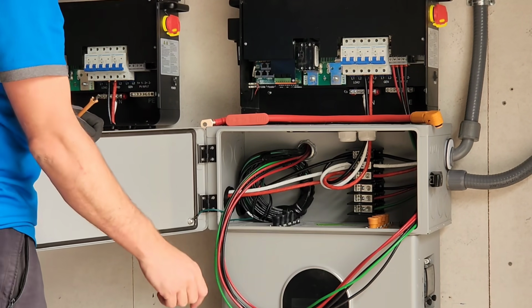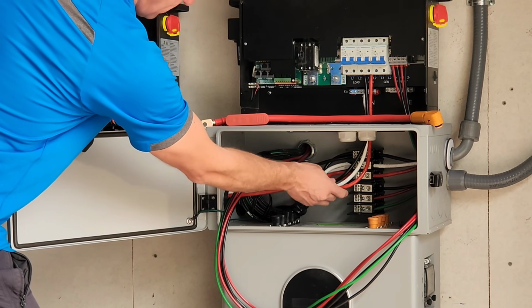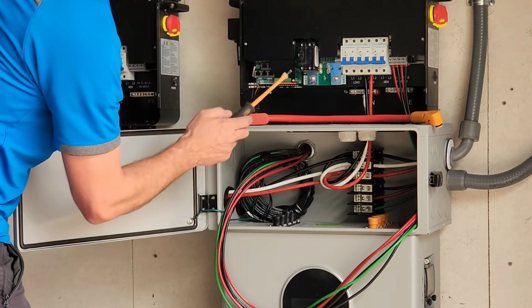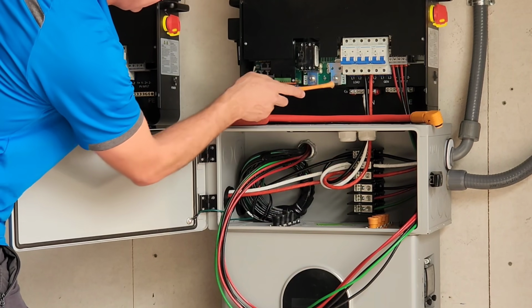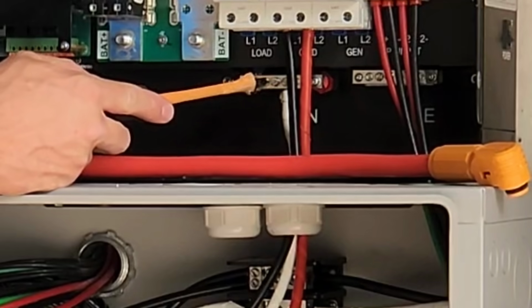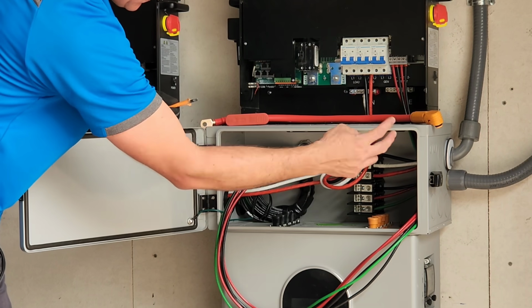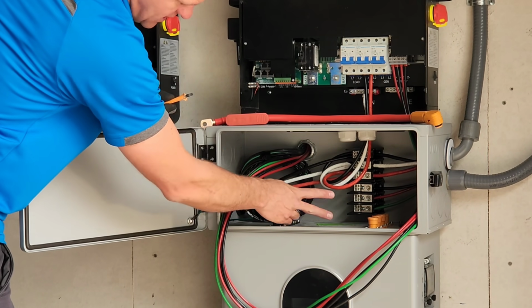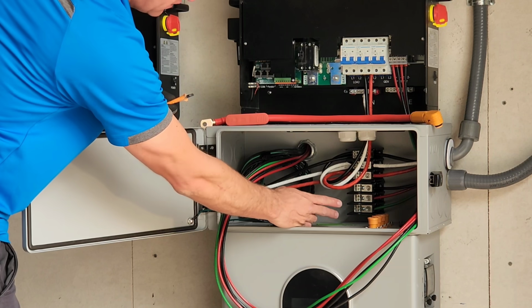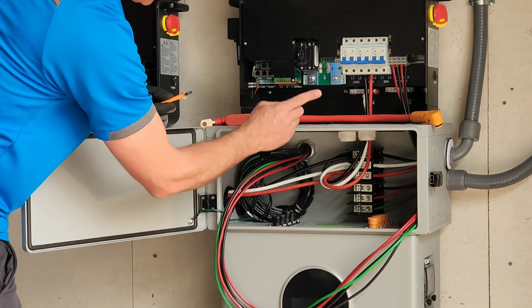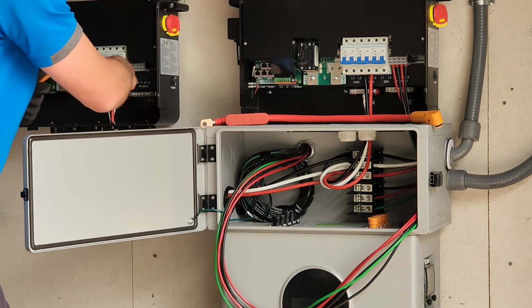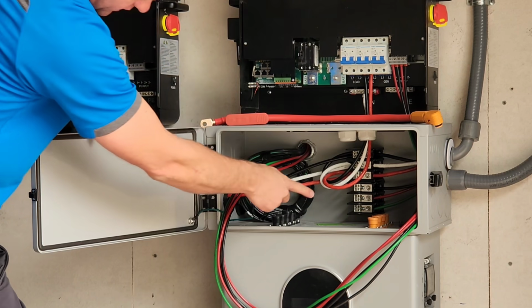Now this is all number 4 wire for AWG. Now I would not go thicker than number 4 wire because it really had a hard time fitting into this bus bar here. So I need to send power into my backfed breaker. So I'm going to tie into the output load here and the output load here into this power distribution block.